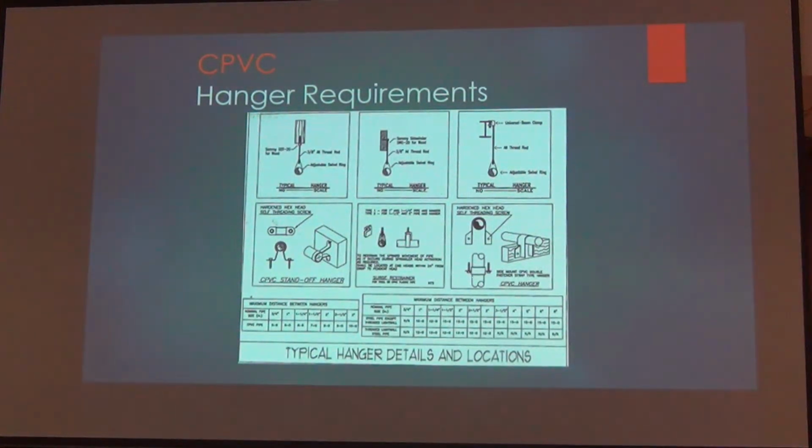Yes, sir. On your drawing here, if that's CPVC on the top 3, is that threaded rod supposed to come down to within 1/16 of an inch on all manufacturers? Yeah. Okay. That's why I said get the manufacturer's information book, because 1/8 of an inch without a surge clip is acceptable. But here's what they all say, at least the last time I read them, that threaded rod can come down within 1/16 of an inch of the pipe, but it must be deburred. Are you gonna climb up there and check them all? Seismic movement of the building will wear a hole in that pipe. Surge clips are a whole lot quicker and easier. They just put them on, clip right in there, and life is good.